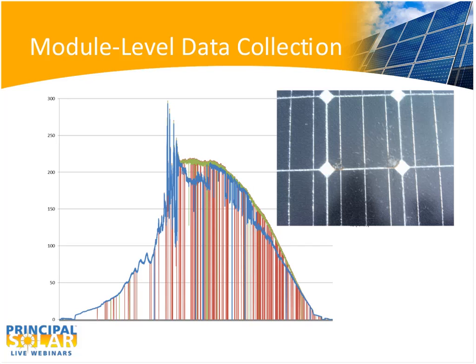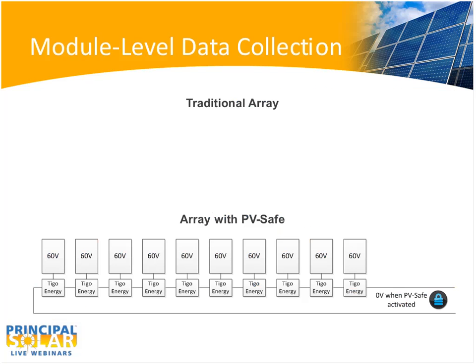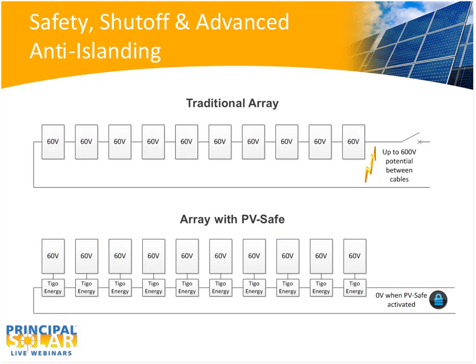With our module-level data, we can actually see the pattern of what's happening. If there's a problem, we can generally tell the difference between a low voltage arc, a bird that died and happened to land on your module, or some other weather-related issue. Finally, as I've mentioned a couple of times, the last benefit of having module-level electronics is that we can shut off each module individually.